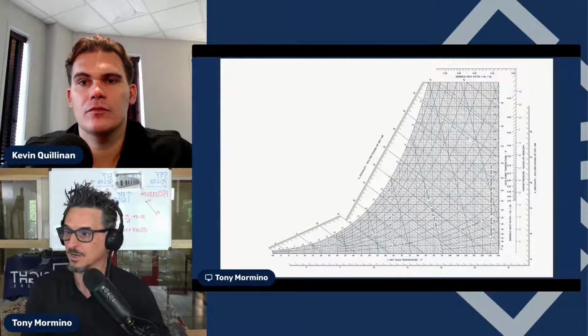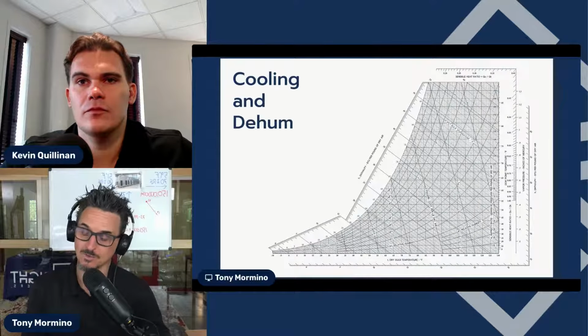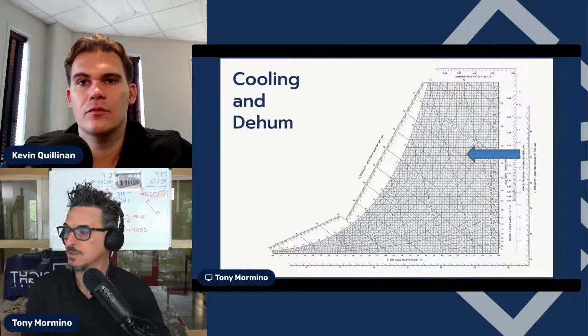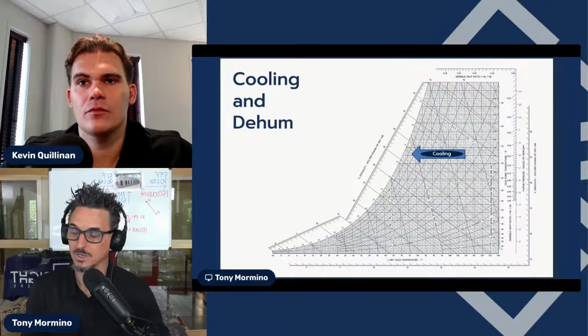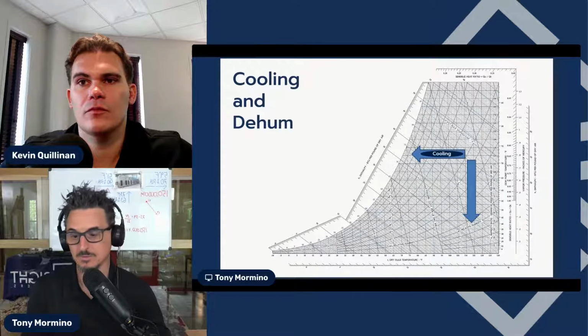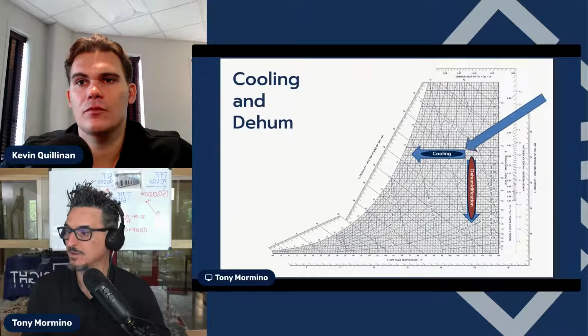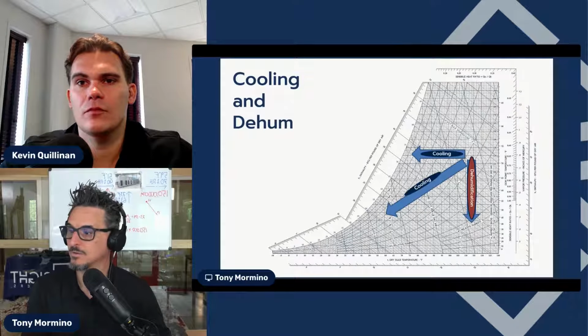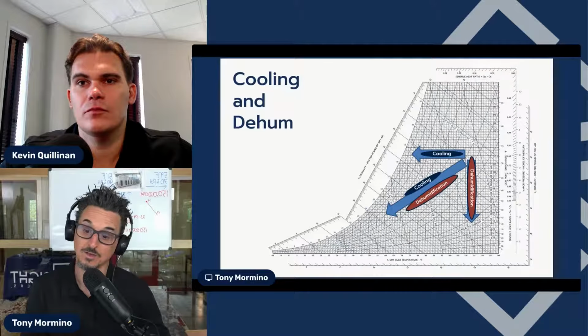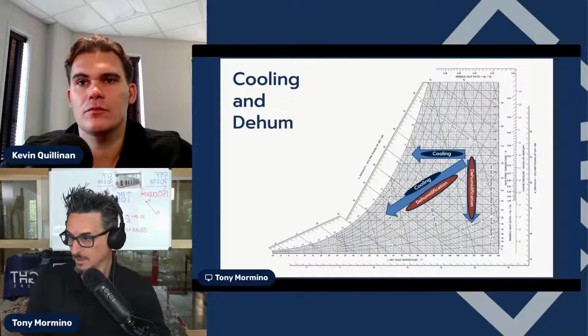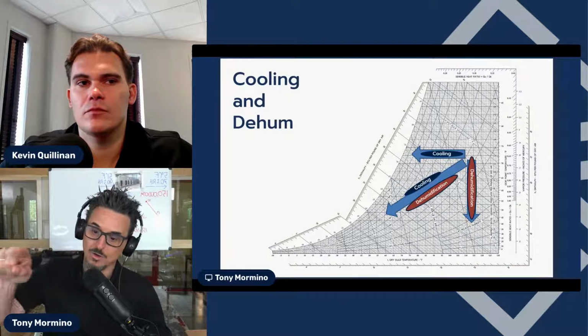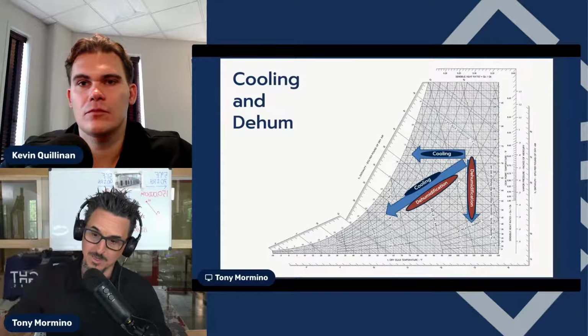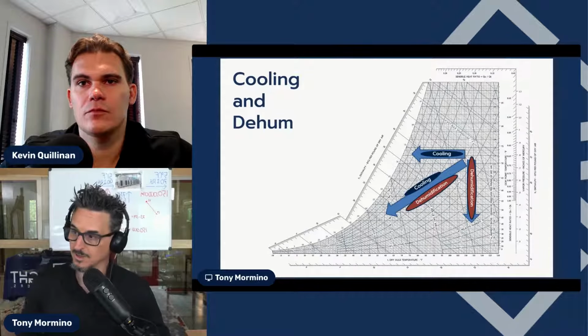When we talk about cooling and dehumidifying, which is what we do with cooling coils in air conditioning systems, we're cooling, going from higher to lower temperature, and dehumidifying, removing moisture, in grains. We typically do that in this fashion. If you look at a cooling coil curve, it goes sensibly for a while, then starts dipping down—that's cooling and dehumidifying as it moves in that direction.